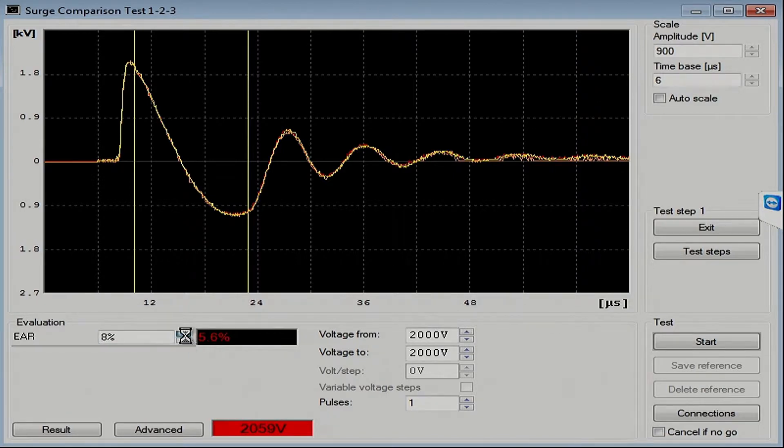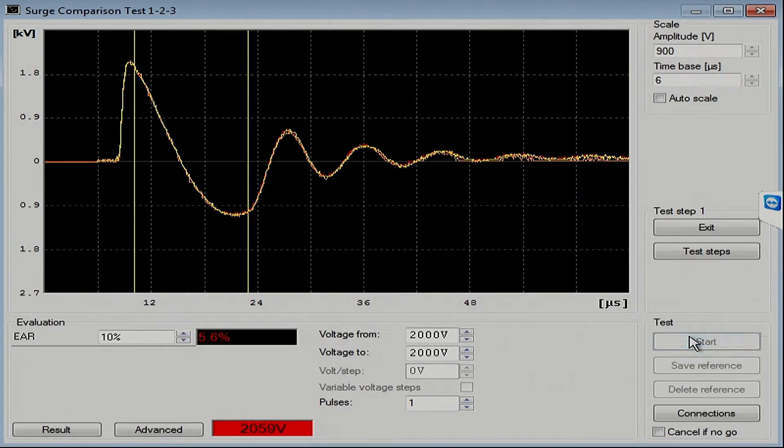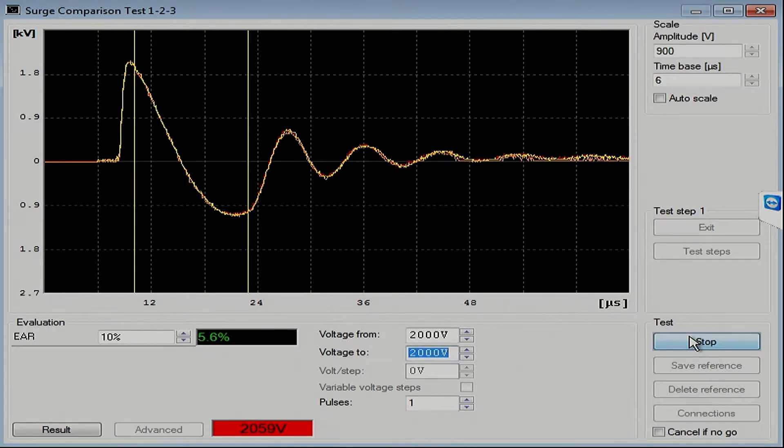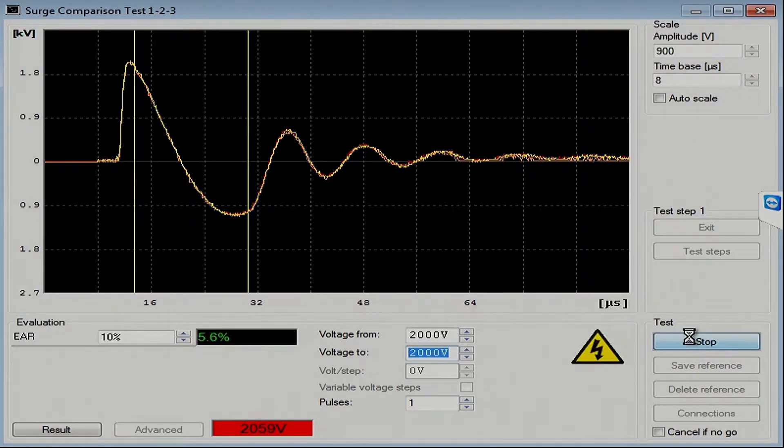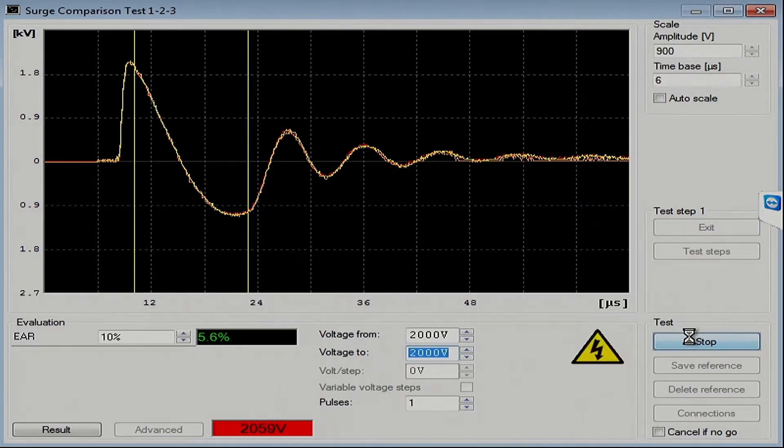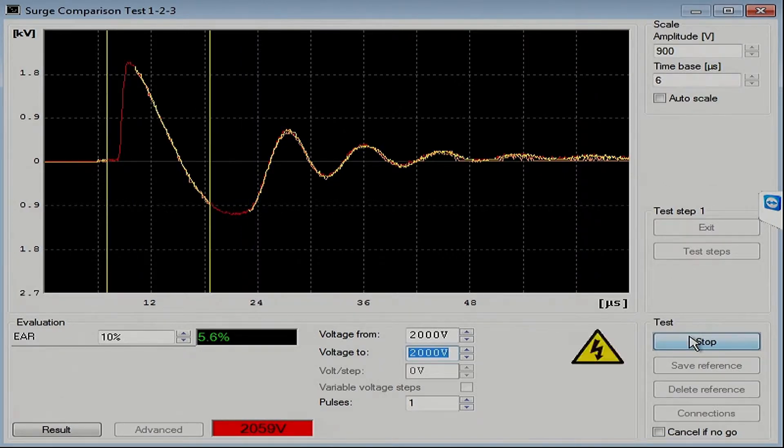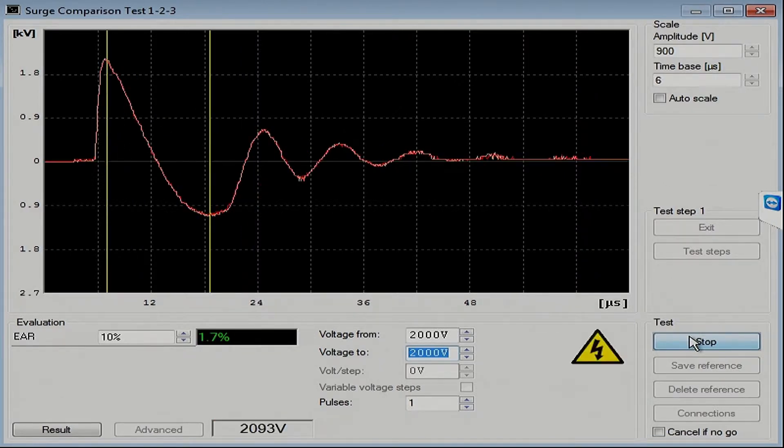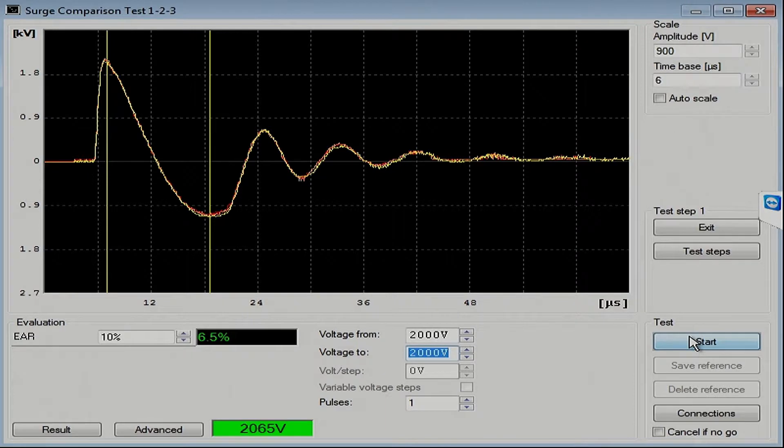Let's increase that to, say, 10 percent, and try it again. There we go. There's our three pulses of the surge comparison test.